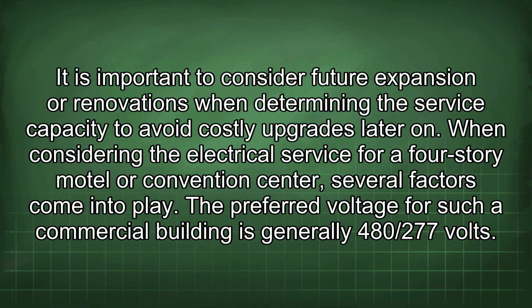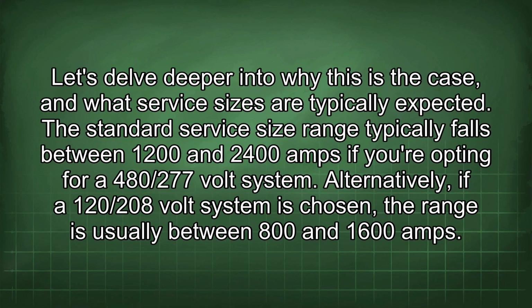The preferred voltage for such a commercial building is generally 480/277 volts. Let's delve deeper into why this is the case, and what service sizes are typically expected. The standard service size range typically falls between 1200 and 2400 amps if you're opting for a 480/277 volt system. Alternatively, if a 120/208 volt system is chosen, the range is usually between 800 and 1600 amps.